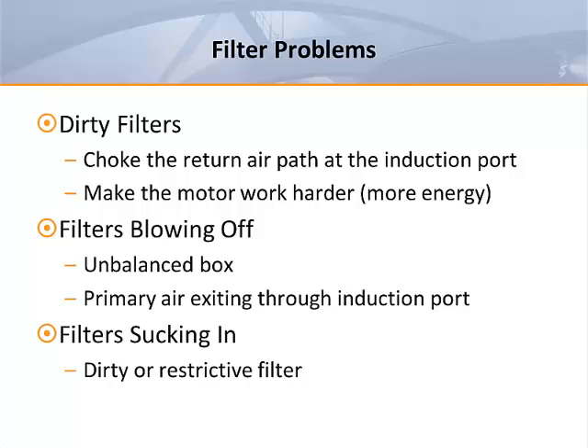Then there's the problem of filters being sucked into fan powered units. This can occur as filters become dirty or if highly restrictive filters have been installed. I recently spoke with a building owner who installed MERV 13 filters and had this very problem. Although the engineer had specified MERV 7 filters after construction, the building owner found MERV 13 filters from a local supplier, figuring he was getting better filters. Well he was, but the ECMs on the units were strong enough to suck these filters in.